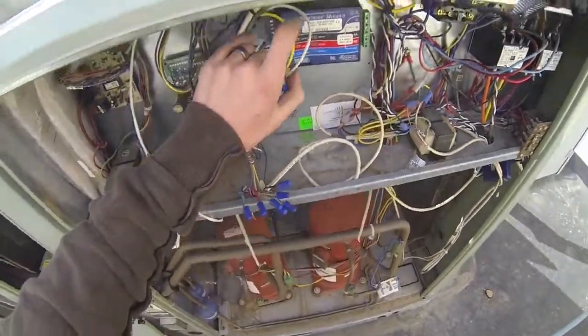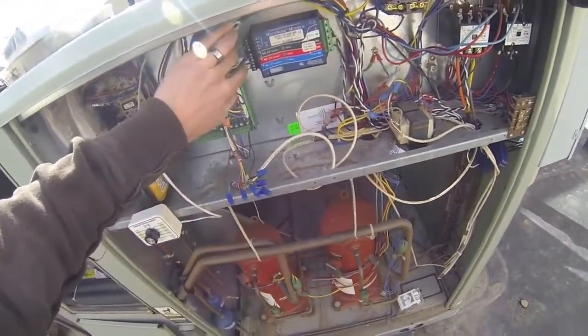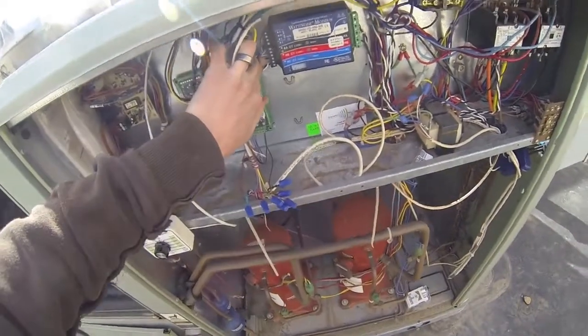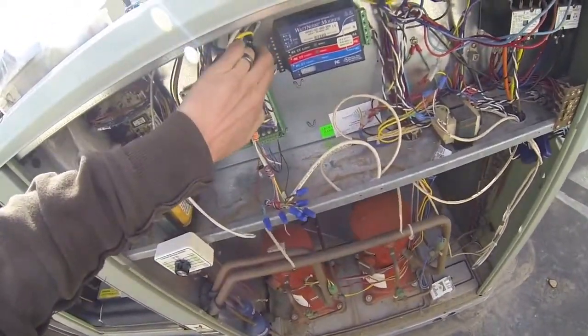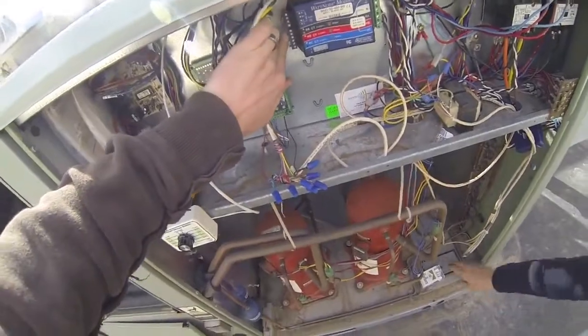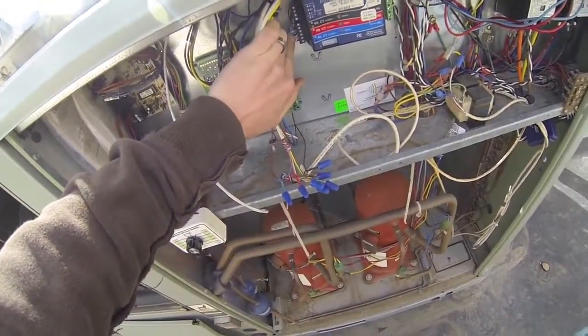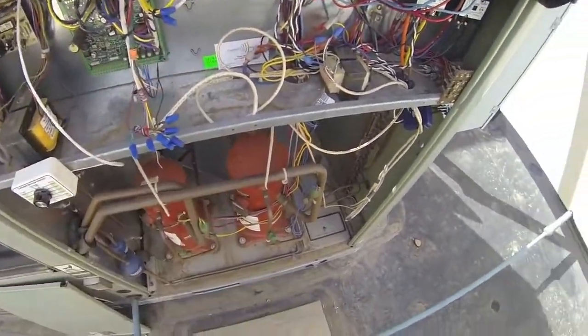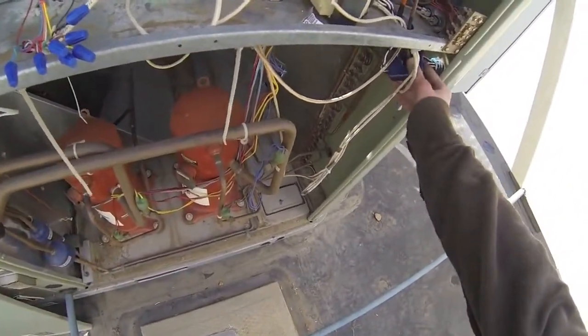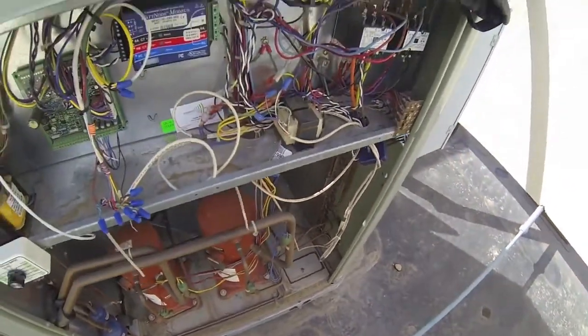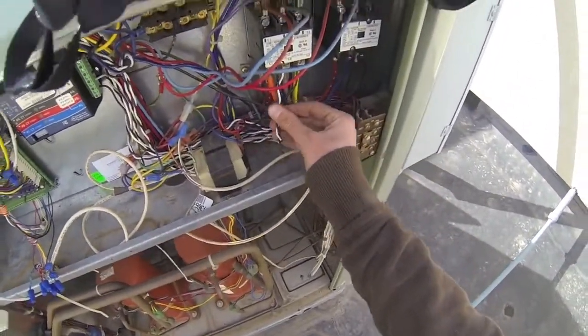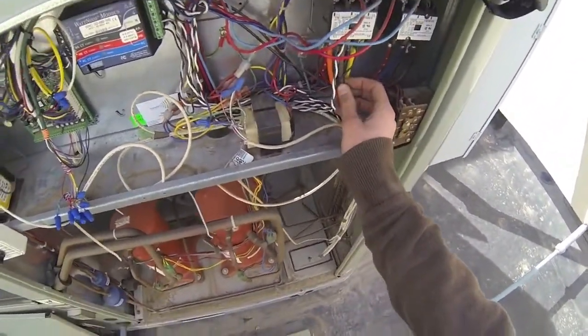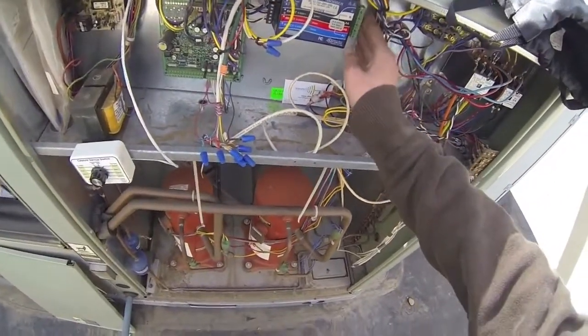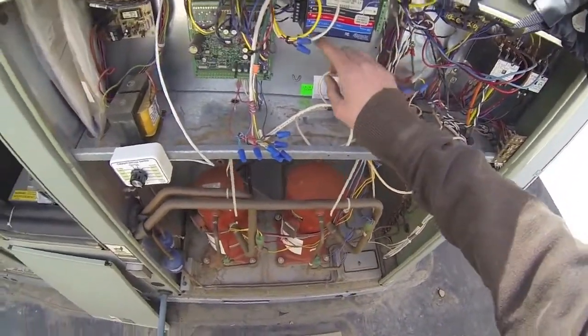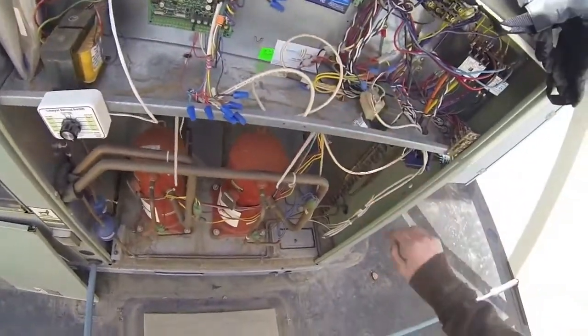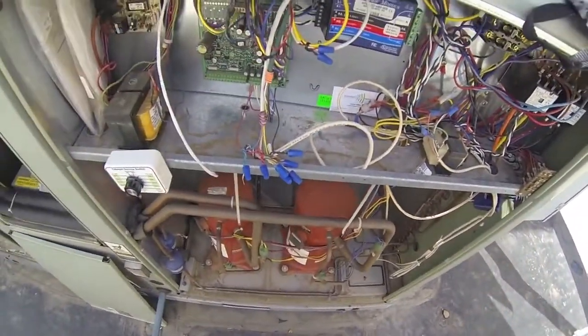We have our watt node, which we use a comm wire, our blue 2 conductor, which has black and white. Black goes to A minus, white goes to B positive. Then we wire up our CTs, which measure the amps, and then we run voltage wires that go on right where the line voltage is coming into the unit. Voltage goes on this right side, and make sure we keep the same continuity with the leads.